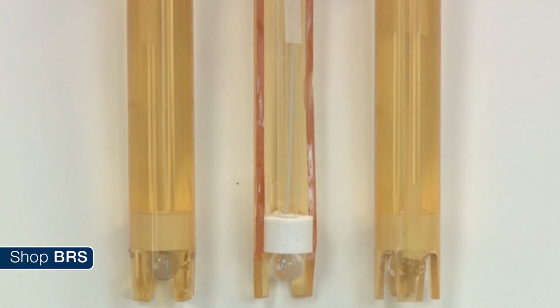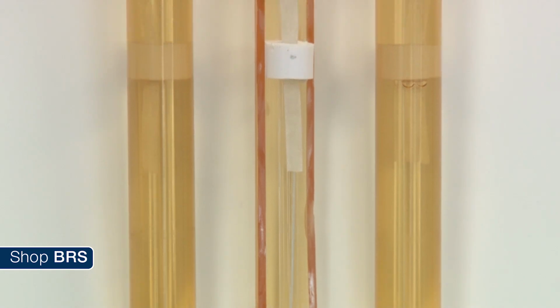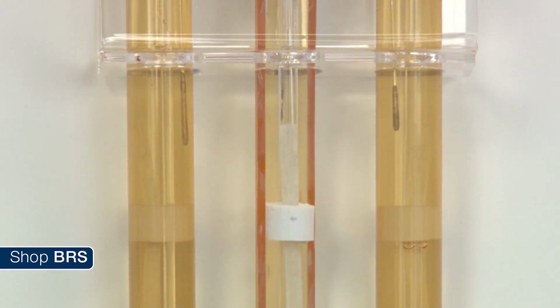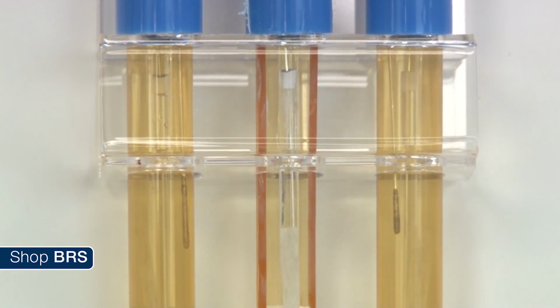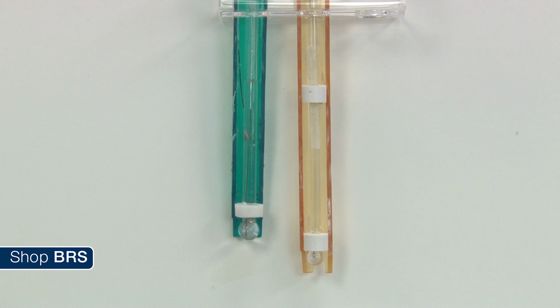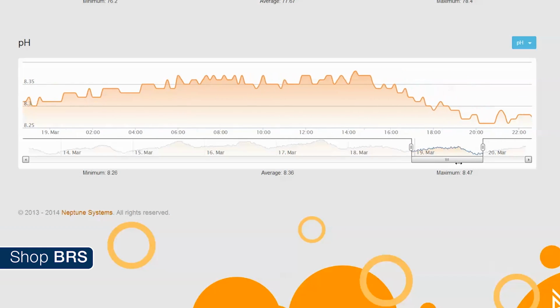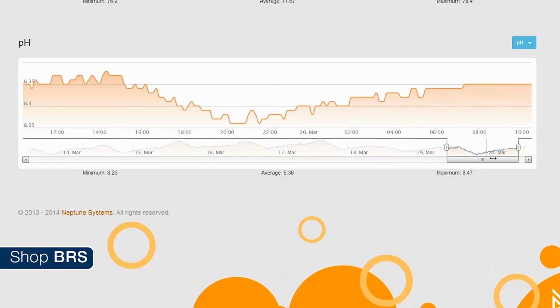On the opposite end of that spectrum, if you use a high quality probe, particularly double junction probes, you can often go a lot longer between calibrations, and the probe will last a lot longer because the probe's second junction protects it from all the proteins in the aquarium water, which will eventually cause the probe to drift and/or need to be replaced.